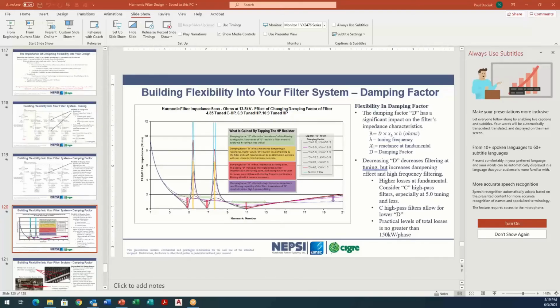That's a good question. This is a situation where the grid code requirement is that the system be inductive. Harmonic filters, by their nature, are capacitive, which means that you have to put in a shunt reactor to compensate for the harmonic filtering. We just had a project about a year ago where the system needed a 5 megavar shunt reactor to compensate for a 5 megavar C-high pass filter that was part of the system for the light load condition.